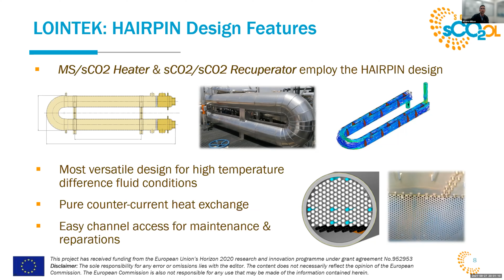In the case of the recuperator, we have around a 350-degree temperature drop. In the case of the heater, as we said before, it's around 200 degrees. So this design is the optimum choice to avoid thermal shocks and thermal stresses within the units. As the hairpin design is divided into two legs, there is pure counter-current heat exchange within the unit. As with most shell and tube heat exchangers, we also have easy channel access for maintenance and repair purposes if needed.